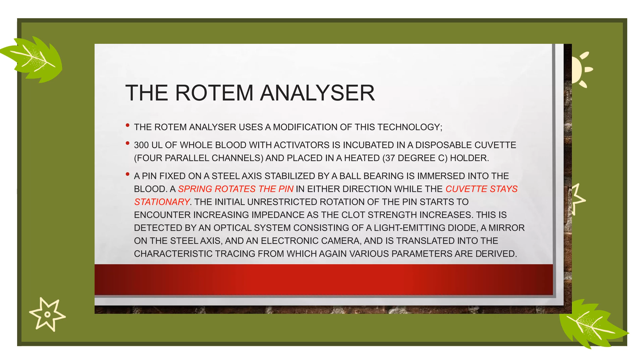The initial unrestricted rotation of the pin starts to encounter increasing impedance as the clot strength increases. This is detected by an optical system consisting of a light-emitting diode, a mirror on the steel axis, and an electronic camera, and is translated into the characteristic tracing, from which again various parameters are derived.